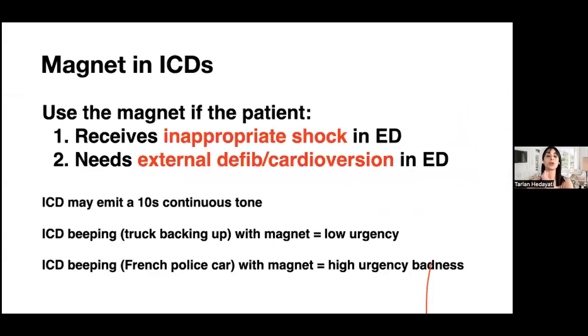Magnets and ICDs, we're going to use that really in one of two scenarios. One is if I see the patient gets an inappropriate shock in my emergency department. They're in front of me, I've got them on the monitor, everything looks good, and for whatever reason the ICD decided to defibrillate them or cardiovert them, which is very uncomfortable for the patient. I'm going to put the magnet on because I don't want the device to do that. It's inappropriate, I want to make sure I turn the device off.